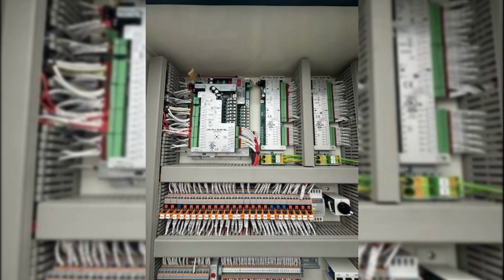When it comes to the control system, a gateway is required anytime the native controls are not BACnet. That could mean Modbus, Profibus, or another protocol. The gateway must fully translate all proprietary logic into BACnet, so the DUS building management system, an open protocol platform, can communicate seamlessly. And before anything is signed off, integration testing has to be demonstrated to the commissioning authority to prove the system works as intended.